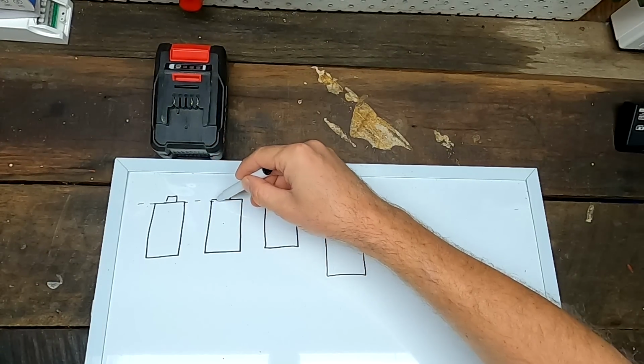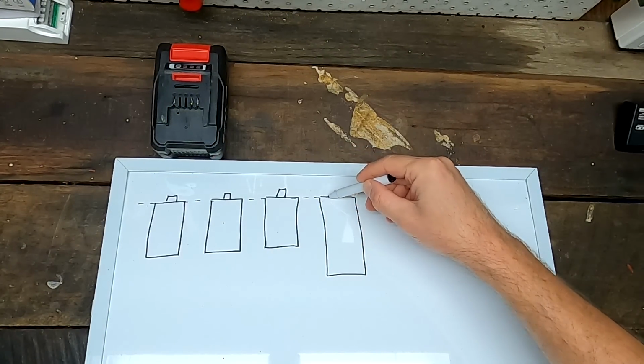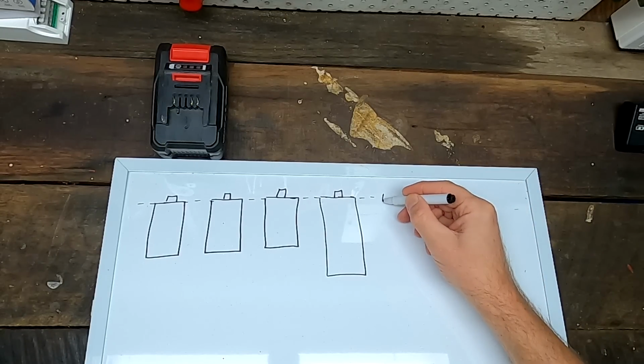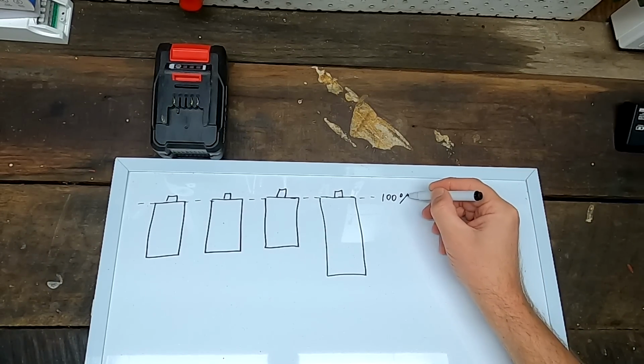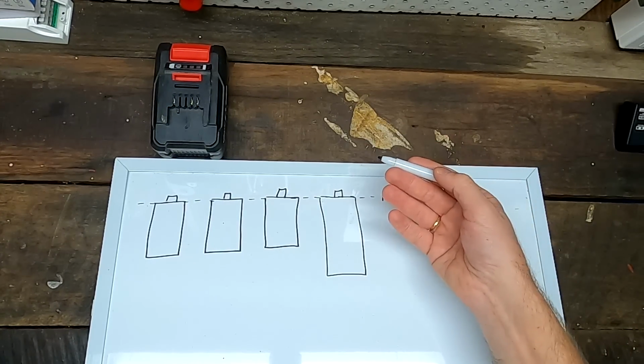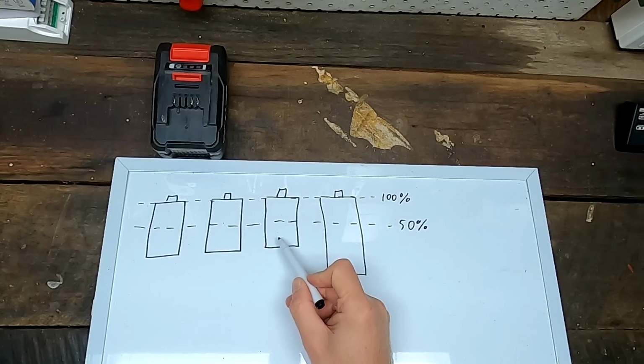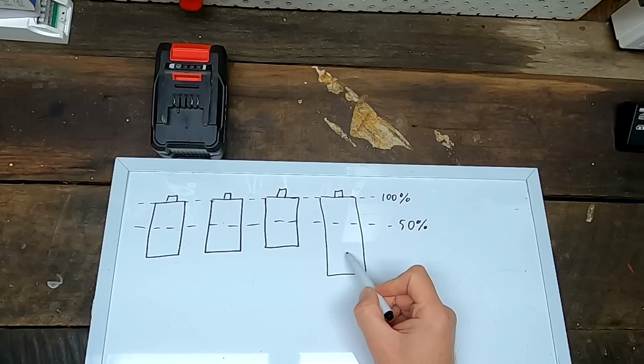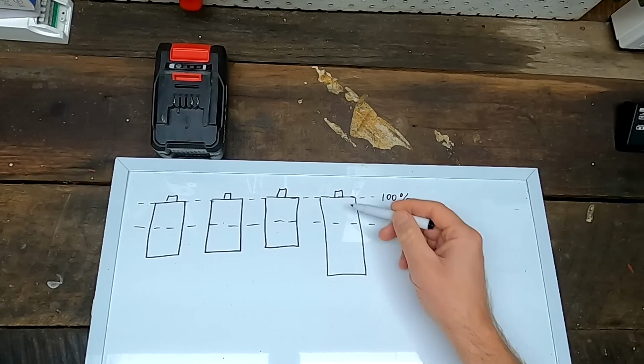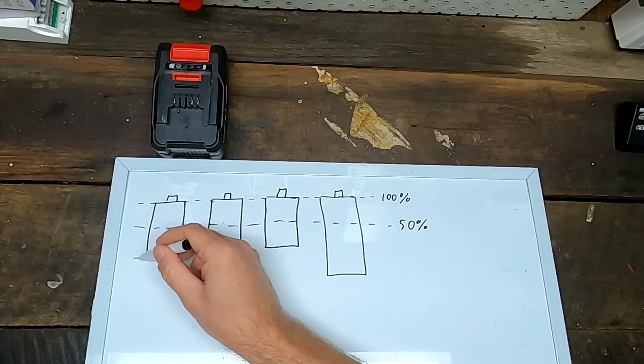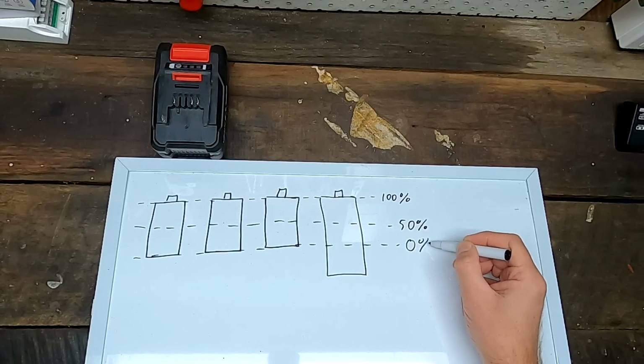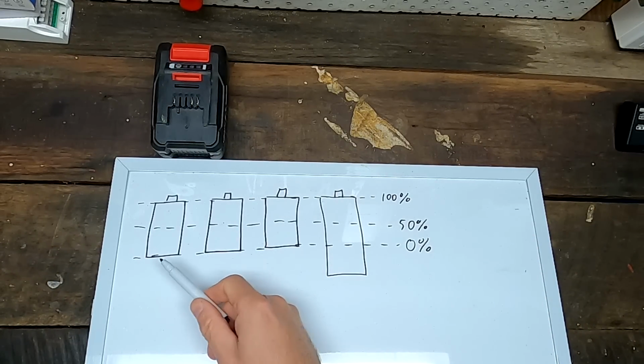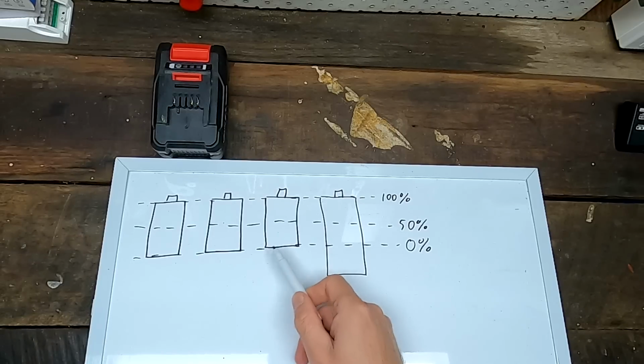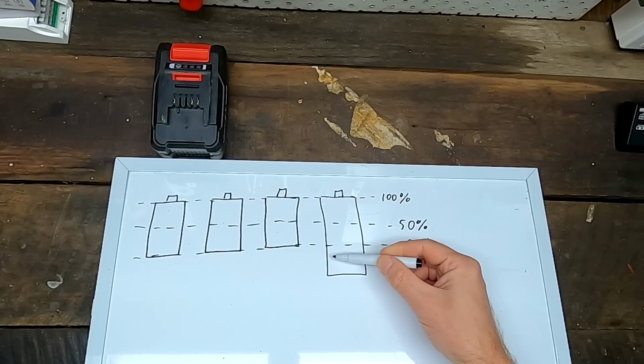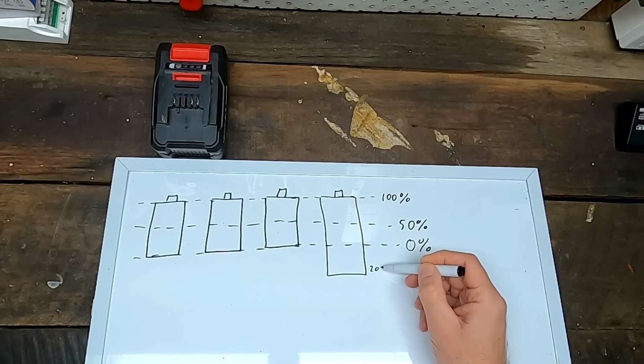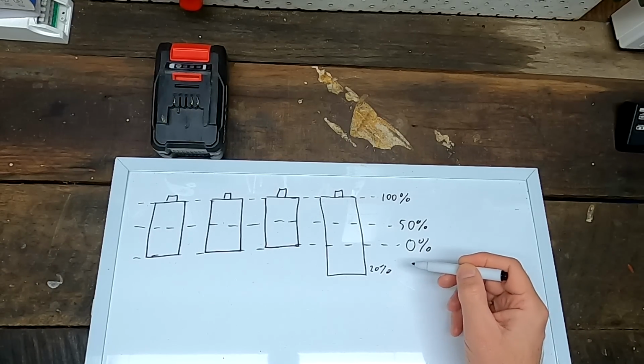At the moment, we all have them 100% charged, so they all have 100% state of charge. If I discharge the battery now to 50%, these 3 batteries may have 50%, but this one may still have 55 or 60%, because it has a higher capacity to start with. And the same at 0%. When we have fully discharged the battery, these batteries are empty, they cannot deliver any more power. But this one may still have 20% state of charge left.